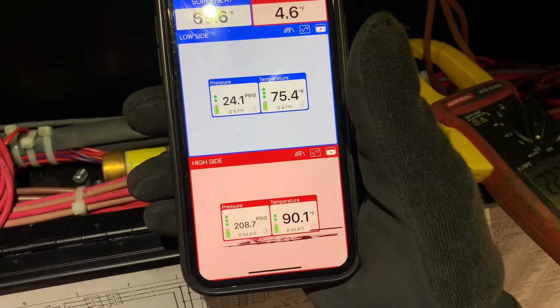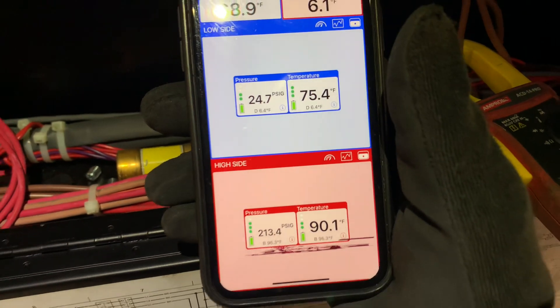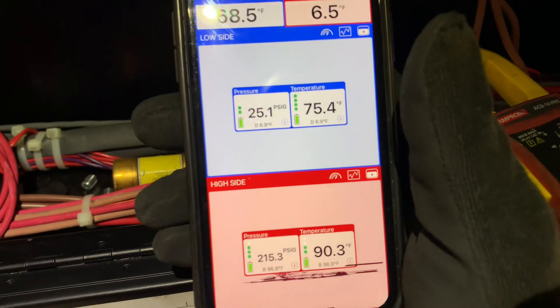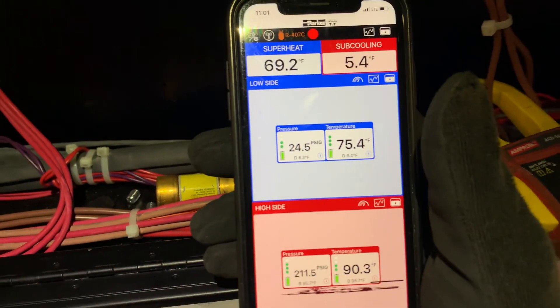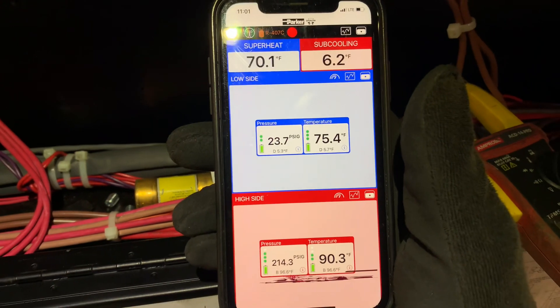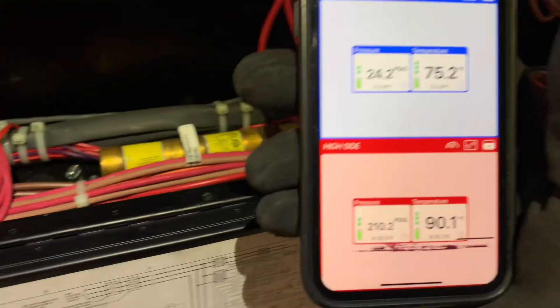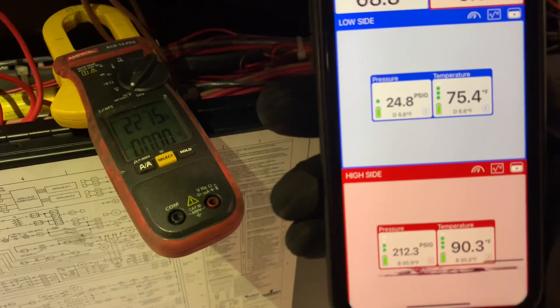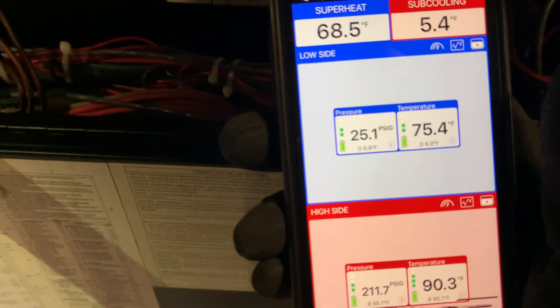The entering fluid temperature is in the 80s, entering the condenser coil. But you can see what's going on from these numbers, the system is, it's not a restriction, it's not a bad TXV, it's low on refrigerant. It's a refrigerant leak. But that's the reason for that freeze protection warning.